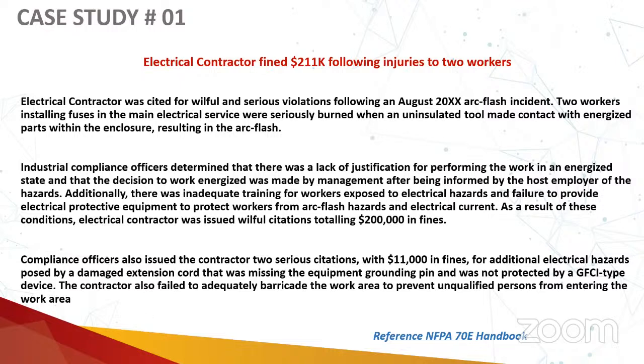Yes, Mr. Modi. Yes, the first observation I can see here is that the tools that the worker has used, or the contractor provided, were uninsulated tools. The other thing is that these 2 workers were directly working on, either it could be arc flash is coming, meaning definitely it could be on 440 volts. And these people were not even provided arc flash suits, either 8 cal, 12 cal, 24 cal, or 40 cal.